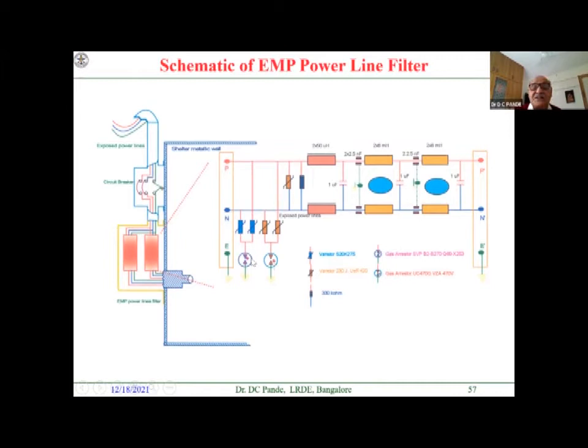These gas arresters, like GD tubes and others, are filled with radioactive material so they can respond faster. One has to be careful with GD tubes available for lightning protection, since those respond in microseconds, but here we need nanosecond response, so it has to be chosen accordingly.